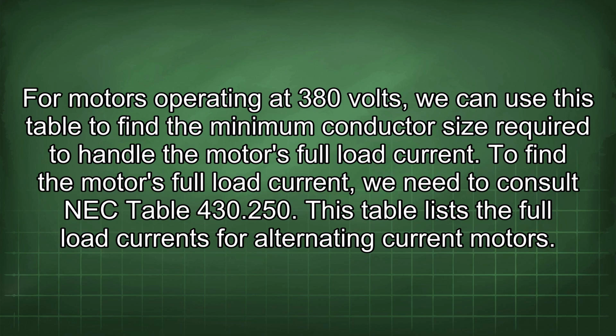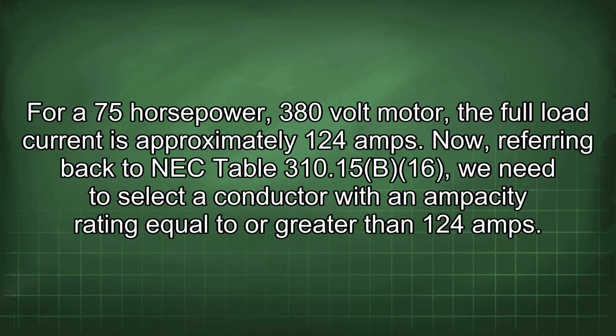To find the motor's full load current, we need to consult NEC Table 430.250. This table lists the full load currents for alternating current motors. For a 75 horsepower, 380 volt motor, the full load current is approximately 124 amps. Now, referring back to NEC Table 310.15(B)(16), we need to select a conductor with an ampacity rating equal to or greater than 124 amps.